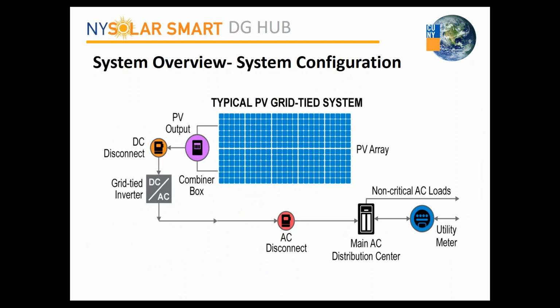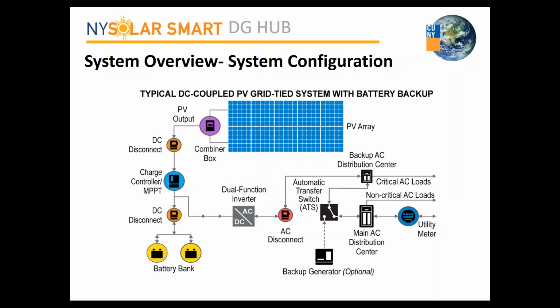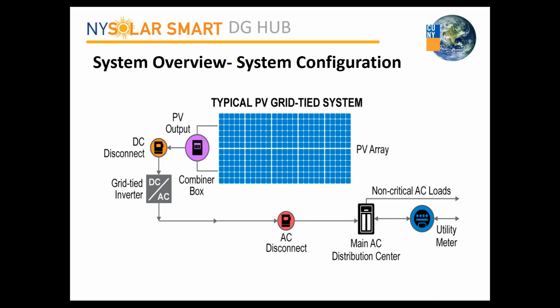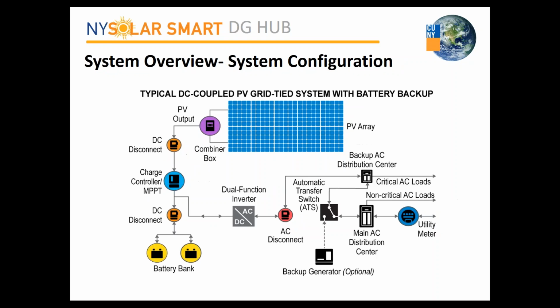I'd like to then talk a little bit about configuration of systems. On the slide here is a typical PV grid-tied system. We start with a PV array, then you have the grid-tied inverter that feeds your non-critical and main distribution system. But as this shows, when the utility goes down, the grid-tied inverter disconnects. In system configuration, we look at tying either to the DC side or the AC side, so we have DC coupling and AC coupling. On the next slide, we talk about that.